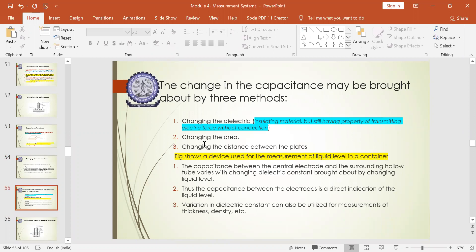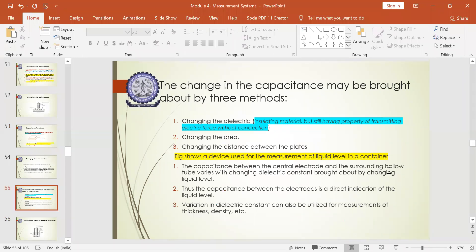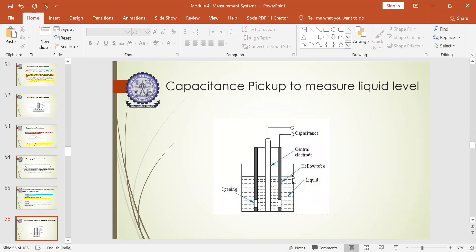Capacitance pickup is used to measure the liquid level in a given container. The capacitance between the central electrode and the surrounding hollow tube varies with the changing dielectric constant. You have a container with a liquid, a central electrode, and an input signal connected to it, along with an output signal that measures the capacitance. The hollow tubes inserted between the central electrode serve as the surrounding tube, and the liquid itself acts as a dielectric medium in liquid form.